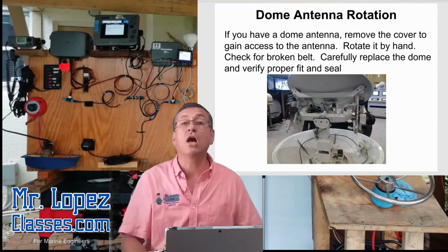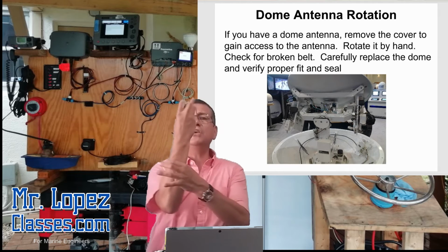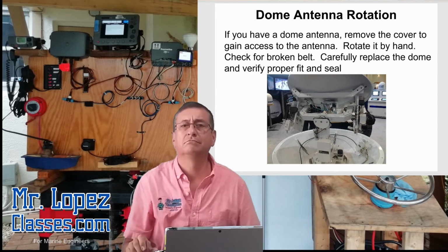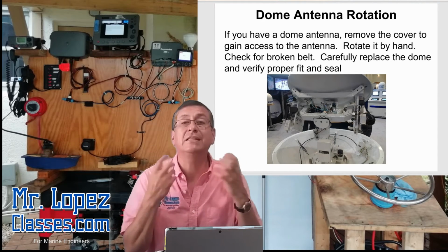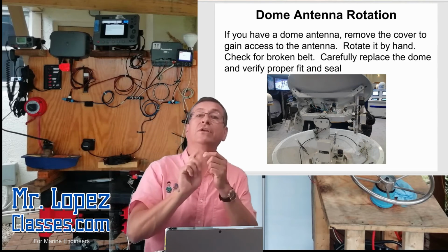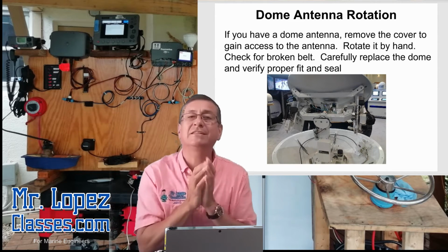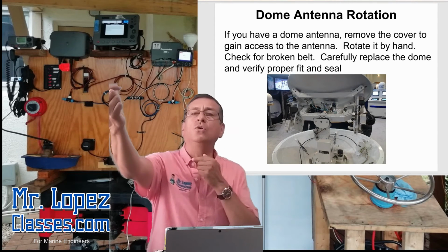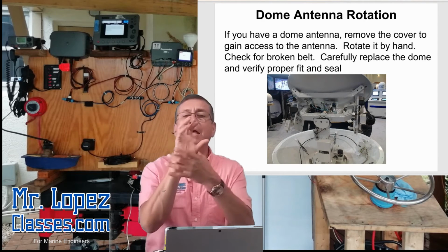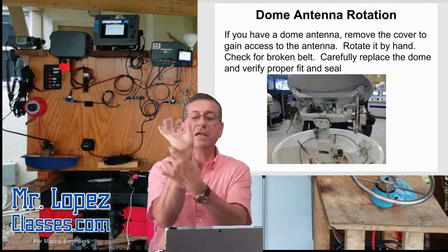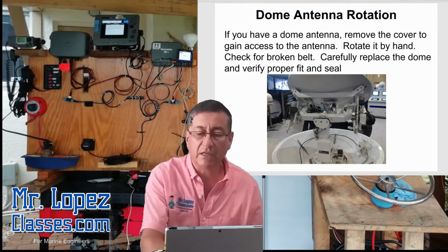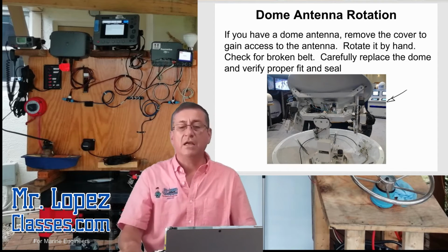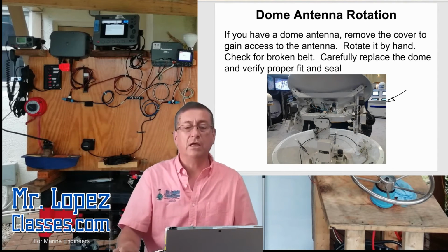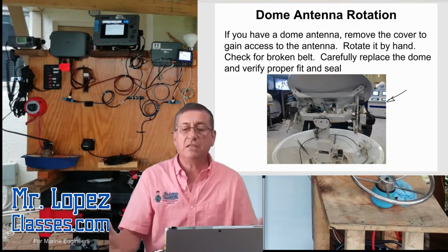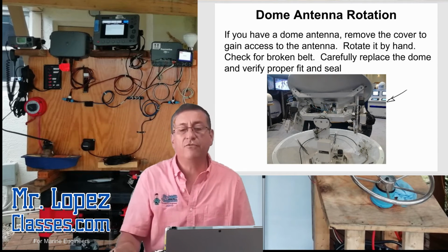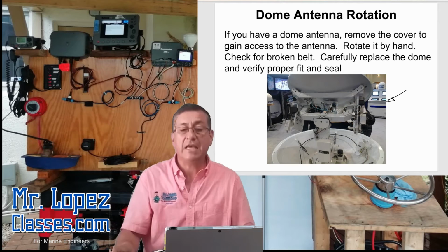All right. If you have a dome, internally in the dome you have the dish rotating 360 degrees. And the dome is a special plastic. That plastic allows the rays to enter and go out. It's a special plastic. That plastic is not an insulator. That plastic allows the rays to pass and bounce. All right? And the disc is rotating 360 degrees internally, like this disc with the mechanism that you have on the screen right now. If you have a dome antenna, remove the cover, the plastic, in order to access the antenna. Rotate it by hand. Check for a broken belt. Carefully replace the dome and verify proper fit and seal.